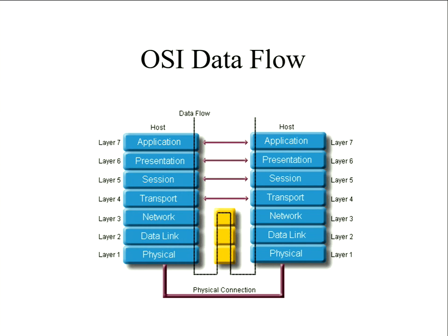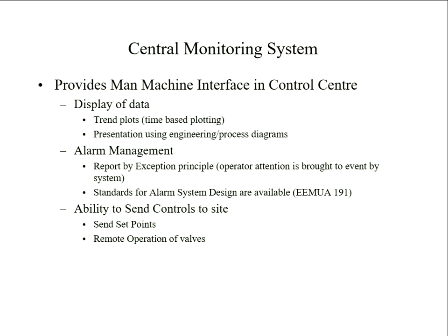And there are various standards for alarm system design. EEMUA 191 is, I think, it came out of the chemical industries, but it's been used a lot in this country as a reference point. People have tried to come up with more sophisticated alarm handling systems, almost like expert system based. So if I get 23 alarms, what's really the cause, as opposed to the consequence? This was, I think, the Three Mile Island problem, that you start to get alarm floods. Something goes wrong, it causes 3 things to go high, which causes 6 things to happen, which causes 12 things to happen, and the operator gets lost in the morass of alarms and can't spot the root cause.